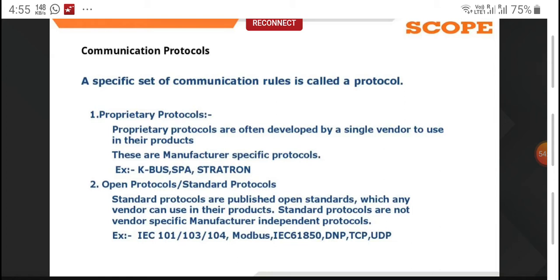Open protocols are normally protocols that are not vendor specific. They are designed by a community or a group of electrical communities who define this set of rules so that everybody follows them. When you develop a product today, and tomorrow somebody else gives you a different product, you want to see both products in your SCADA system, so they should be integrated with it. When you use an open or standard protocol like 61850 or Modbus, it is possible to integrate different manufacturers' products into a SCADA system or automation system. That is the advantage of open and standard protocols.